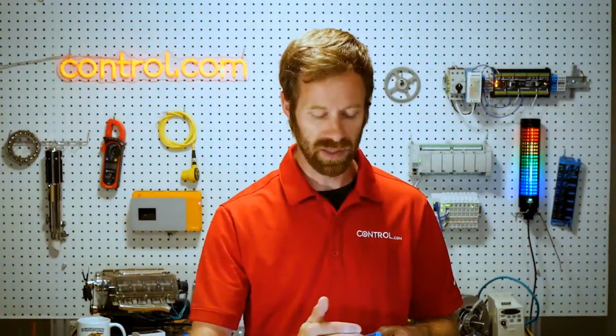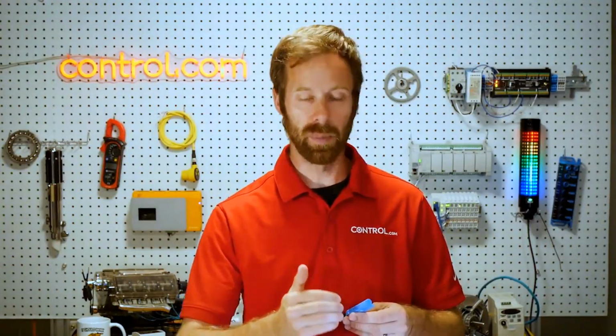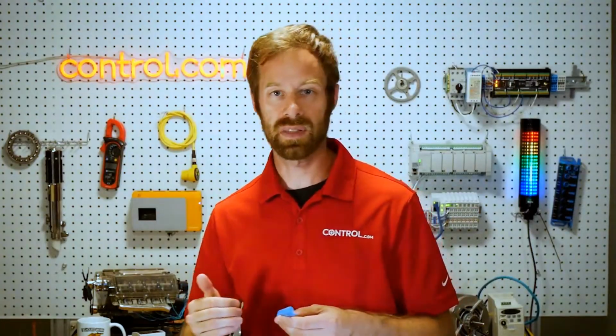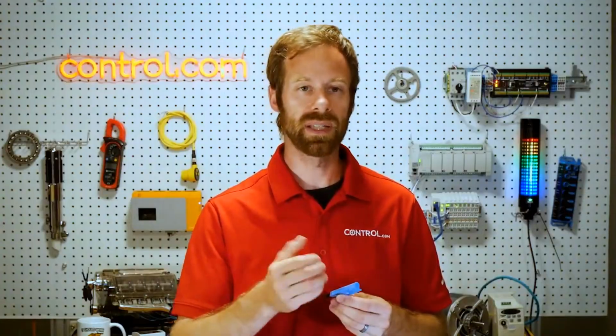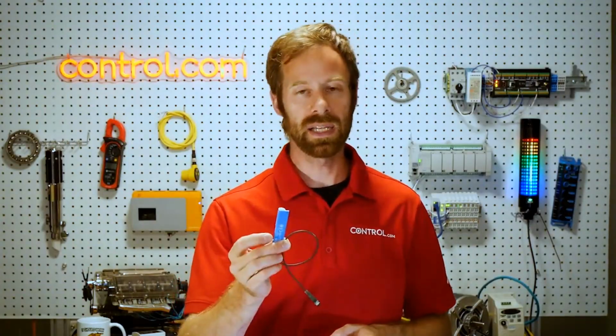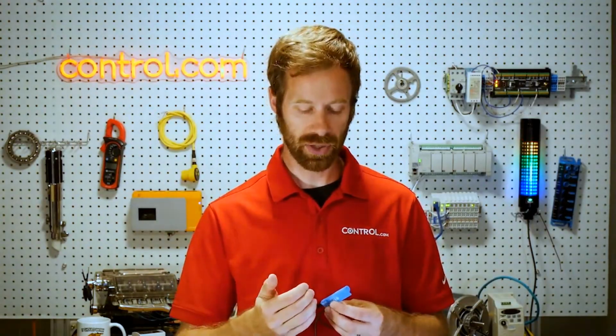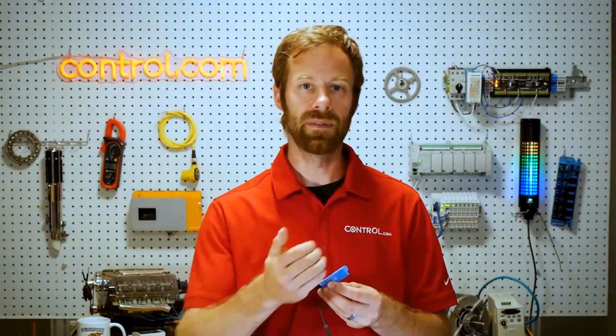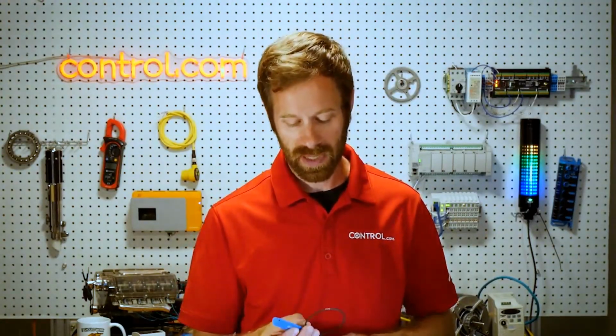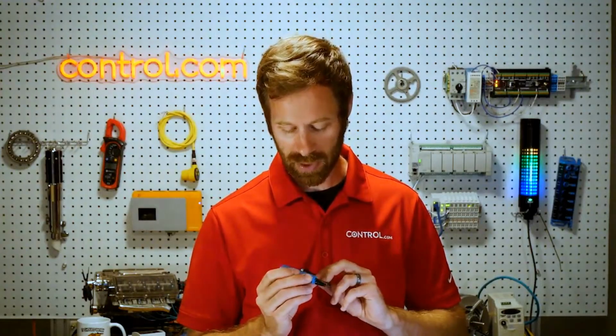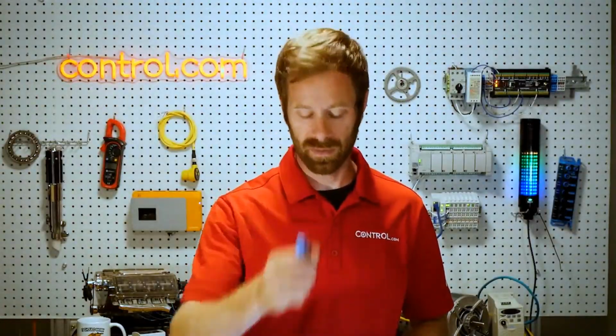So it'll give me limits and settable limit points, so that not only does the cylinder need to travel all the way to the ends, but we can set trigger points at any point that we want and receive the analog value that tells the current value of the cylinder's position at any time. This one also has a complementary analog output, which means it can act as I/O link or as an analog sensor so that my PLC can receive that information.